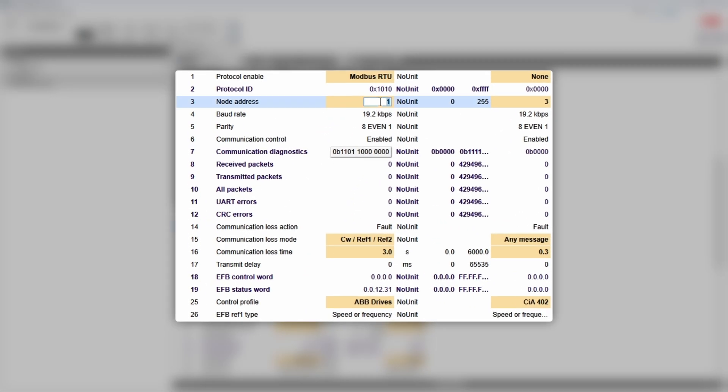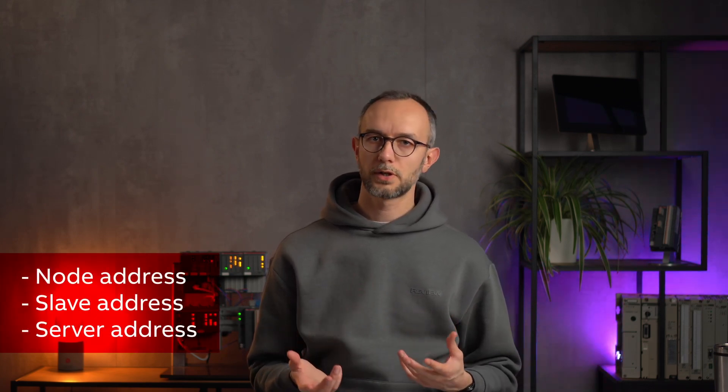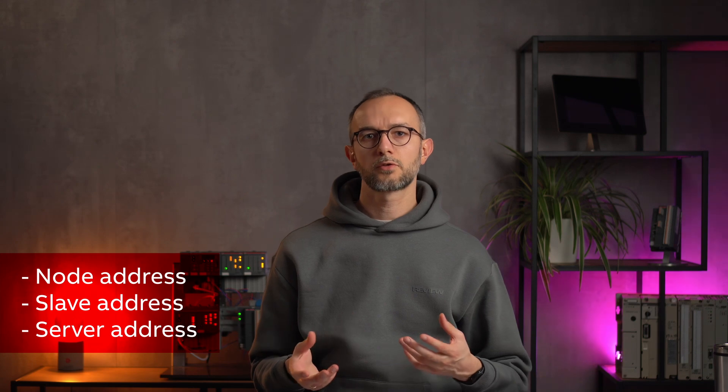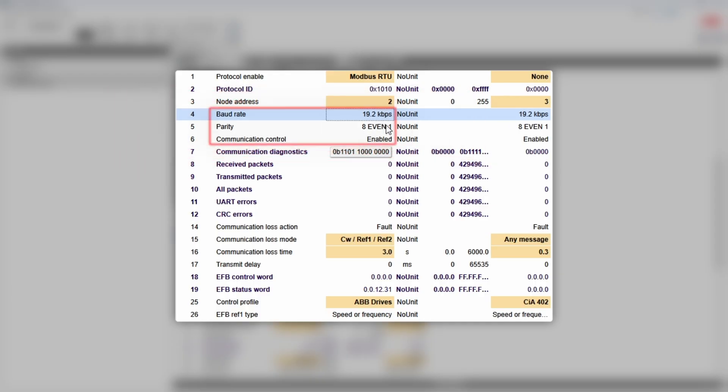First, you need to give the device a node address. You might have heard terms like slave address or server address — in the context of Modbus RTU, it is the same thing: a unique identifier of a device connected to the Modbus RTU line. Then set baud rate, parity, and data/stop bits. The specific values you choose aren't as important as ensuring the settings are identical on both the drive and PLC side.